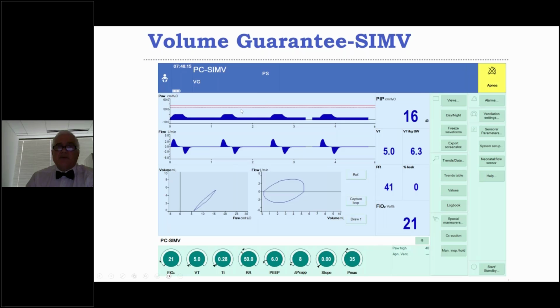When you add in pressure support, and pressure support is not registering here, but again, you will see these minute pressure spikes. Because your volume delivery is so efficacious, it's very important when you're doing SIMV in volume guarantee with pressure support to make sure that these pressure support supplements are not in excess of the pressure that you're actually giving with your volume guarantee breaths. So in this mode, typically a pressure support of 5 is the most that I will give.